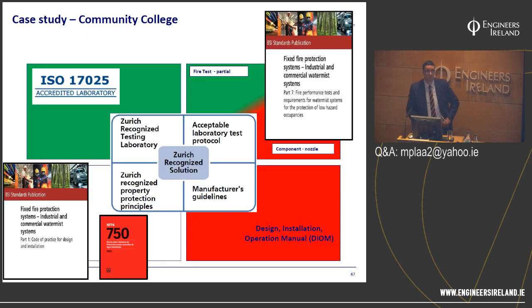And let's pick that apart using our four-stage methodology. We have the accredited test lab, we have the relevant standards, but we have no design installation manual for all of those areas I talked about: obstructions, beams, bays. And most importantly of all, we only have partial fire test data. At the time of analysis of that particular system, we had no component fire test data to fall back on. So this is where this quite simple process is really useful for you to dig a bit deeper below the surface, and see whether what's in a shiny specification is all it's really made out to be.